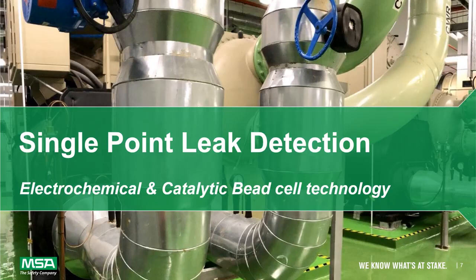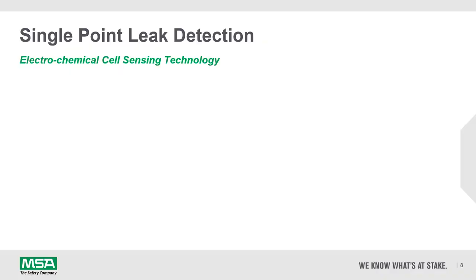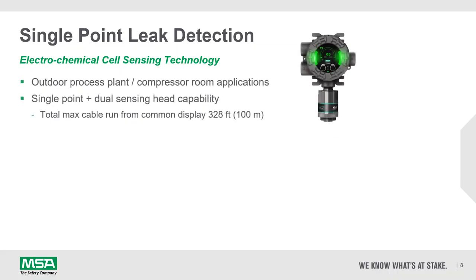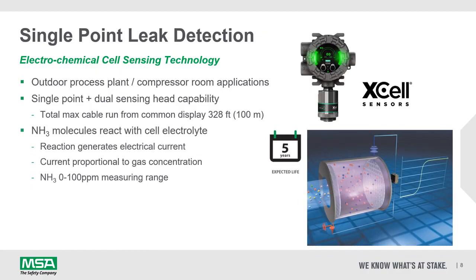Now let's look at single point leak detectors, of which there are two main core sensing technologies being used, one being electrochemical cells and the other being catalytic bead technology. Single point ammonia leak detectors using electrochemical cell technology have been available for a number of years and are typically used in outdoor process plant or compressor room applications. Recent developments have seen the ability to cable two sensing heads to a single display for the benefit of saving cost.